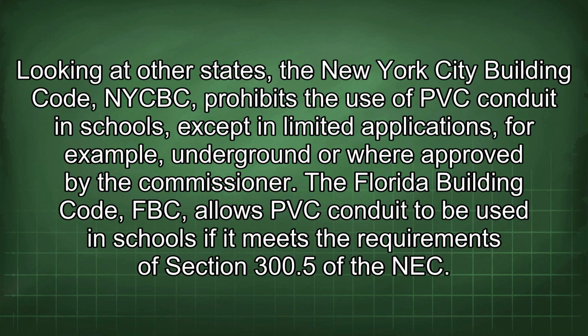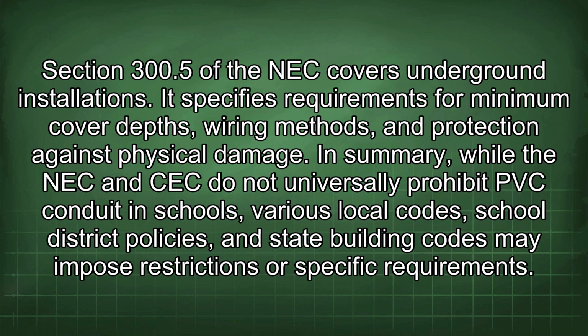Looking at other states, the New York City Building Code prohibits the use of PVC conduit in schools except in limited applications, for example, underground or where approved by the Commissioner. The Florida Building Code (FBC) allows PVC conduit to be used in schools if it meets the requirements of Section 300.5 of the NEC. Section 300.5 of the NEC covers underground installations. It specifies requirements for minimum cover depths, wiring methods, and protection against physical damage.